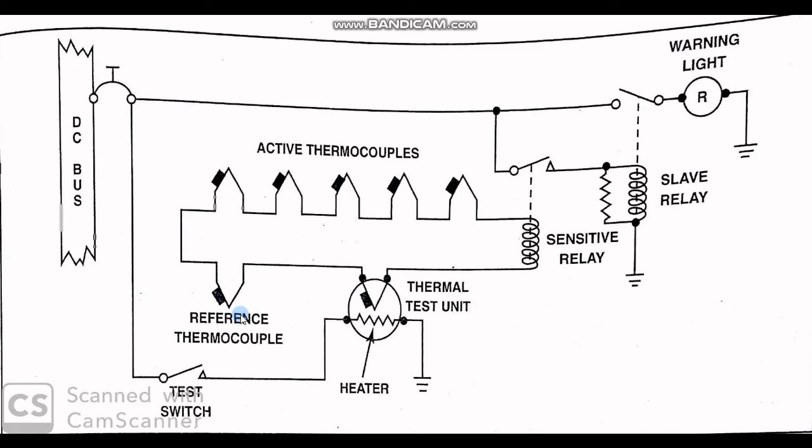Under normal operation, the temperature of the air surrounding the reference thermocouple and the active thermocouples is relatively even, and no current is produced to activate the warning light.